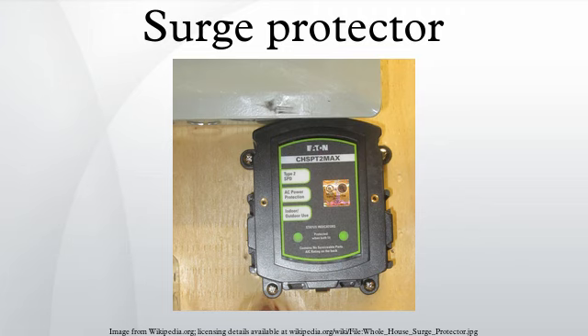Standards: some frequently listed standards include IEC 61643-1, EN 61643-11 and 61643-21, Telcordia Technologies Technical Reference TR-NWT-001011, ANSI/IEEE C62.XX, Underwriters Laboratories 1449. Each standard defines different protector characteristics, test vectors, or operational purpose. The UL 1449 standard for SPDs is a major rewrite of previous editions, and has also been accepted as an ANSI standard for the first time.